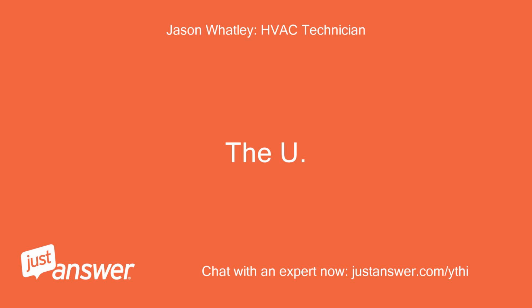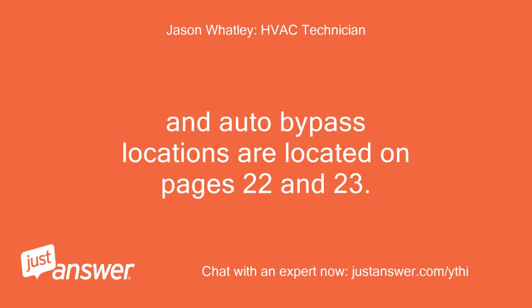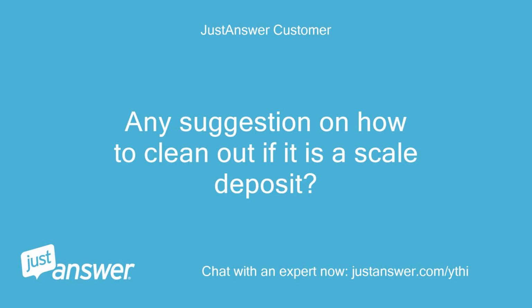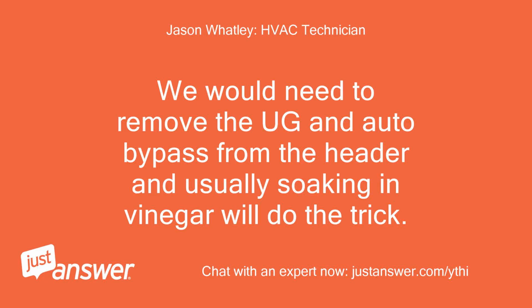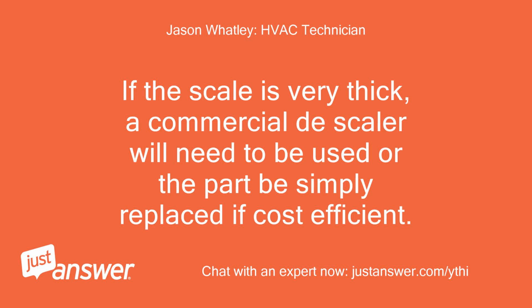The UG and auto bypass locations are located on pages 22 and 23. Any suggestion on how to clean out if it is a scale deposit? We would need to remove the UG and auto bypass from the header, and usually soaking in vinegar will do the trick. If the scale is very thick, a commercial descaler will need to be used or the part be simply replaced if cost efficient.